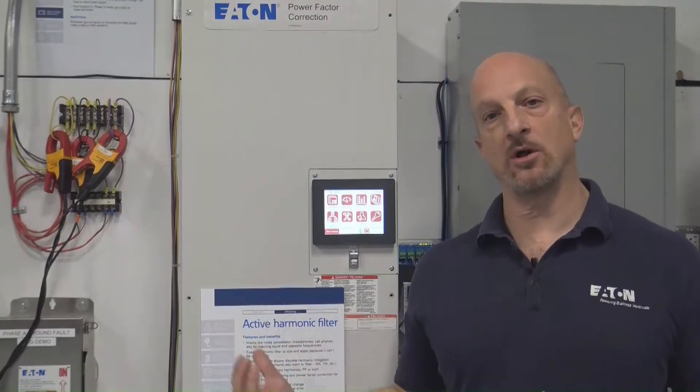Now there is one catch to using these from a system design standpoint. And that is your drive should have either a DC choke or an AC line reactor to minimize the harmonics coming out of the drives. That way, when you use this, you can make this smaller.